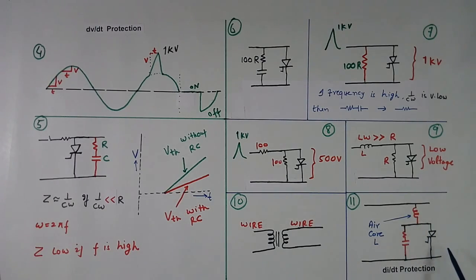This current will flow when thyristor is on. When thyristor is off, current will not flow. But during surges, all drop will be here. This reactor, we have like di by dT protection also. Because in reactor, current doesn't increase immediately. It behaves like inertia for the current. So this reactor limits the di by dT also.